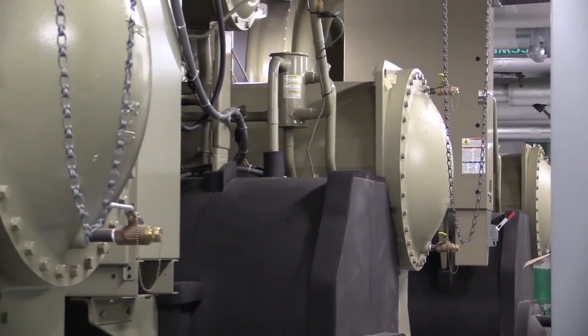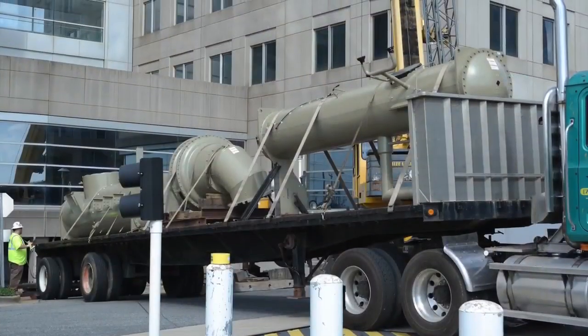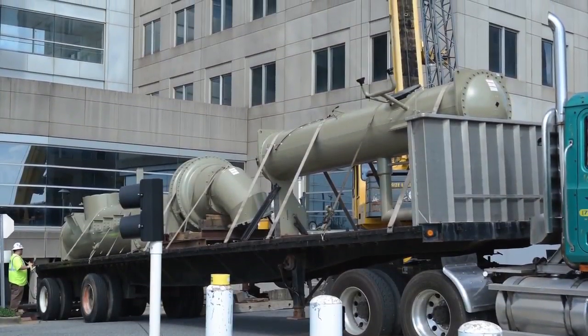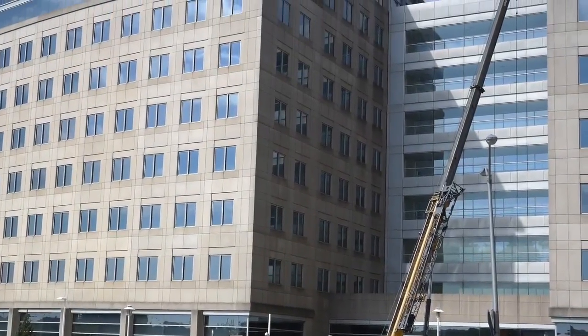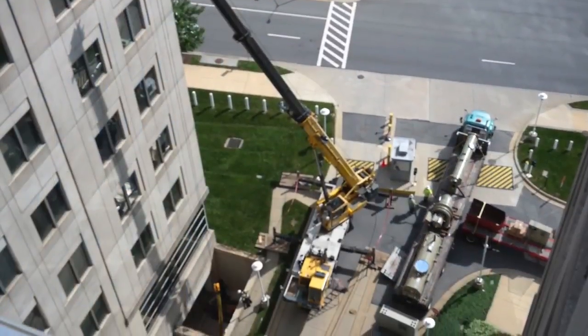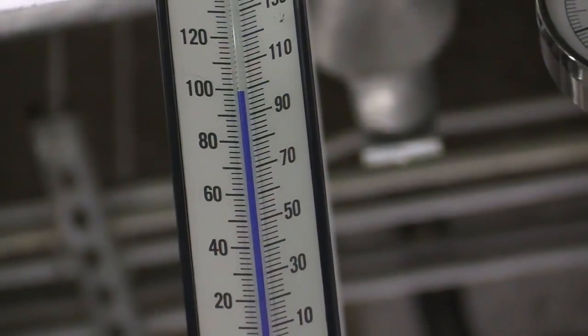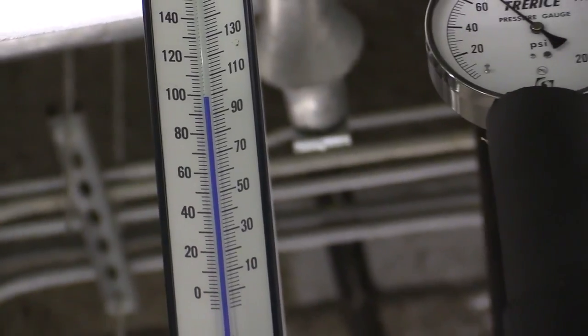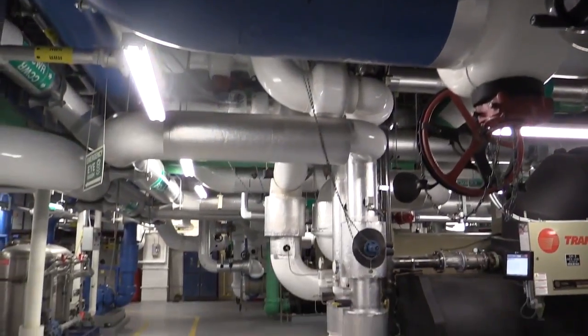We're here in the chilled water plant at the IRS building at New Carrollton. One of the major ECMs that we accomplished was replacing the 3 1,100-ton chillers with 3 new 700-ton chillers. 2 of the chillers provide the cooling for the building. The 3rd chiller is a chiller heater, which provides heating to the incoming air on the roof of the building.